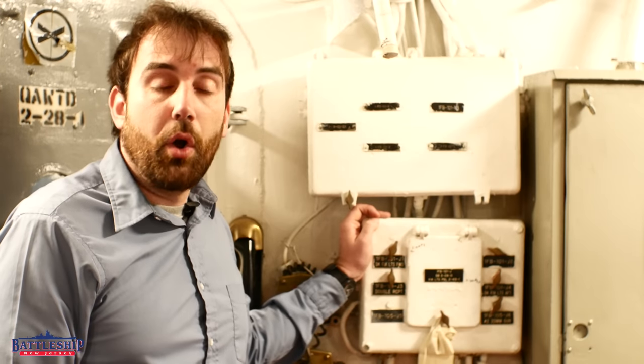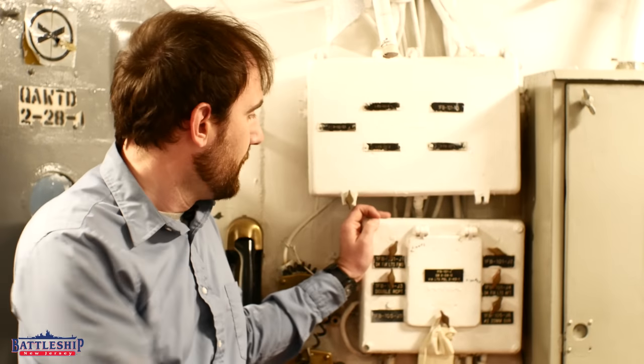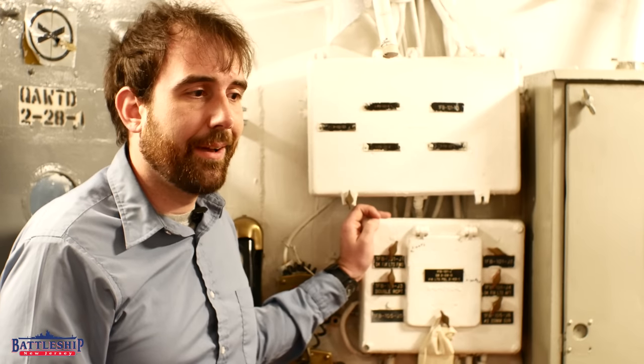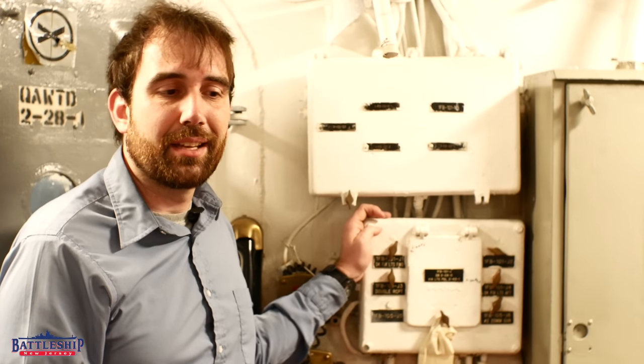In practice, over the years, there were so many additions and so many unauthorized shipboxes and things that the various fuses that feed these fuse boxes ended up all over the place, and it's a real pain to chase them down nowadays. The labels don't necessarily do what they say they did.